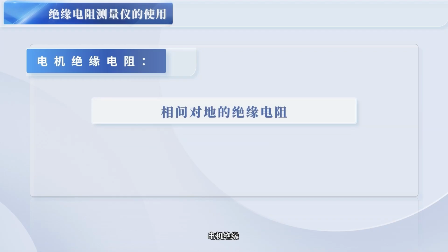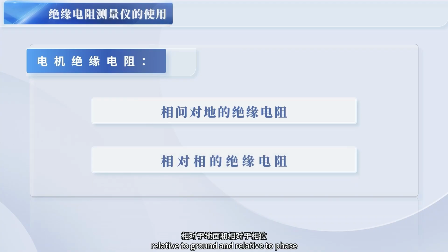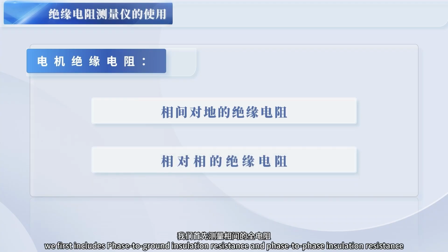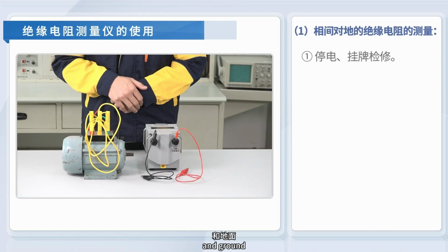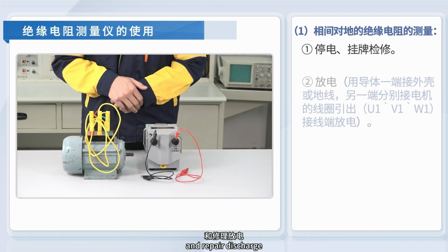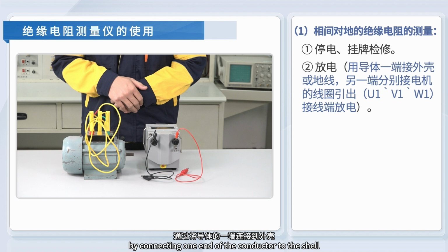Motor insulation relative to ground and relative to phase. We first measure phase to ground insulation resistance and phase to phase insulation resistance. Second, power off, hang a tag, and discharge by connecting one end of the conductor to the shell and the other end to the motor coil. Bring out U, V and W. Third, power on test.